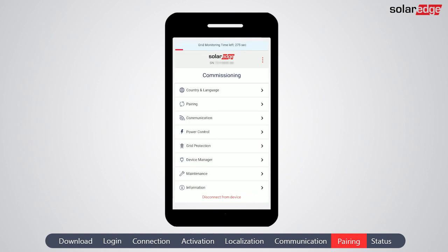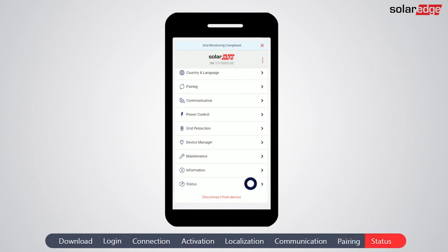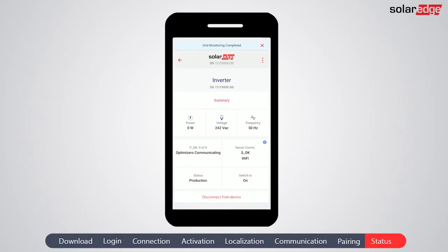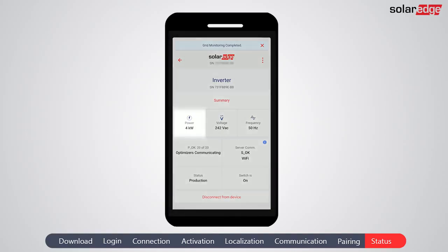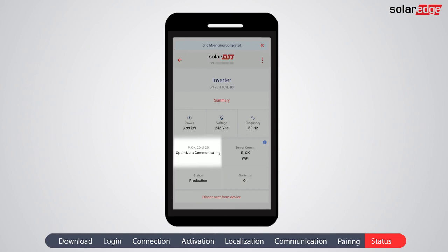Before it starts to produce power, the inverter automatically makes sure that the power it's producing matches the grid parameters. This is called grid monitoring. Once grid monitoring is initiated, you see the banner at the top of the screen. Let's go now to the status screen and verify system readiness. Verify that once grid monitoring is completed, you can see the power increase in the power box. Check that the number of power optimizers on screen matches the number installed and connected to the inverter.